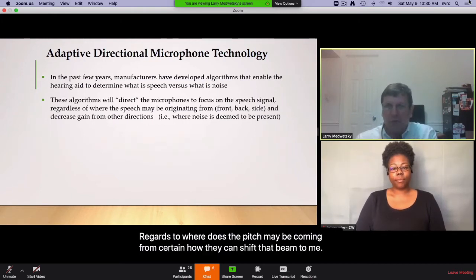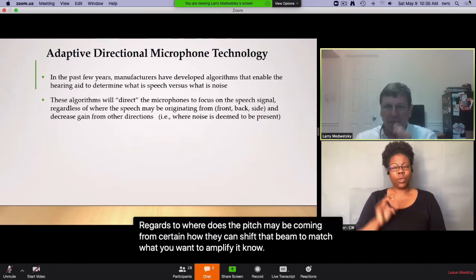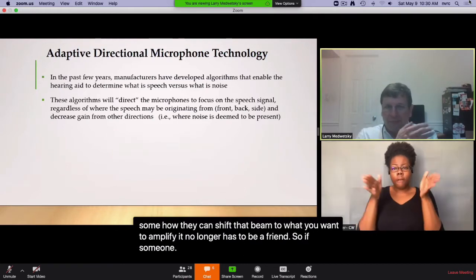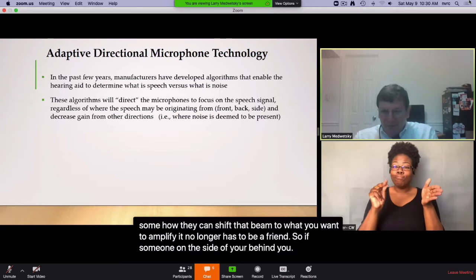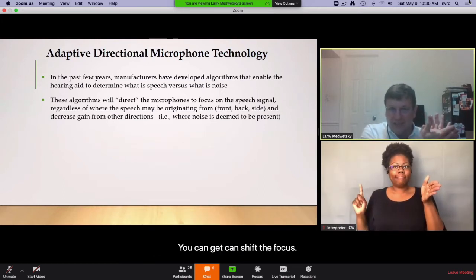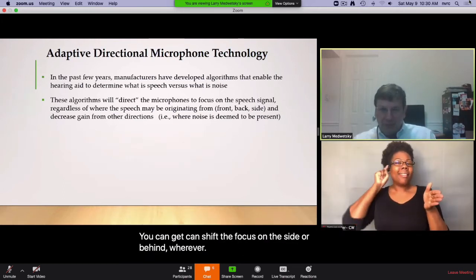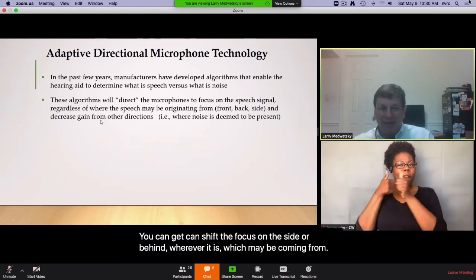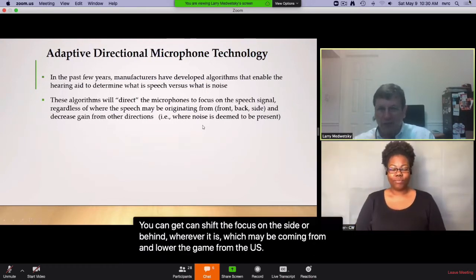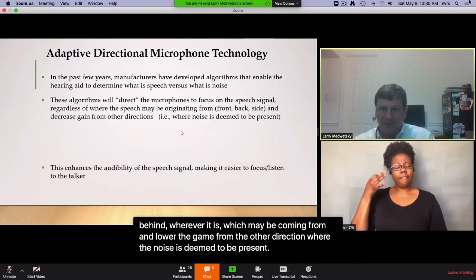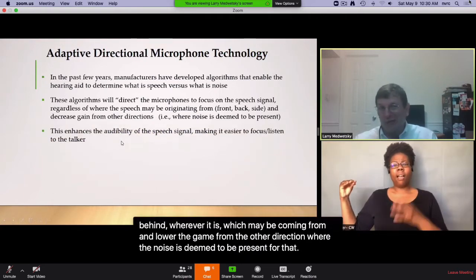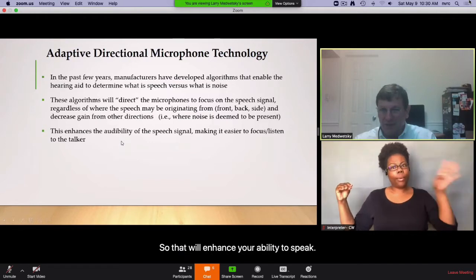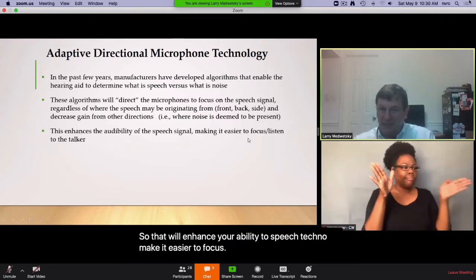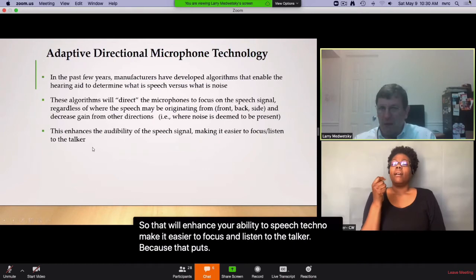So now they can shift the beam to what you want to amplify. It no longer has to be in front. So if someone is on the side of you or behind you, the hearing aid can shift the focus to the side or behind, wherever the speech may be coming from, and lower the gain from the other directions where the noise is deemed to be present. So that will enhance the audibility of the speech signal, making it easier to focus and listen to the talker, because that's what's going to be more amplified.